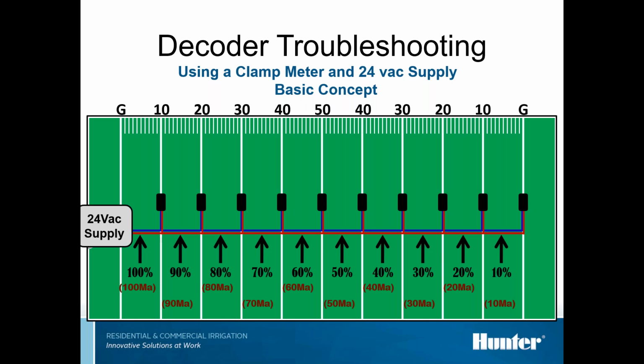And there's a representative of it, but they're using a 10 milliamp, which is perfectly fine too. You ought to be dropping every time you move your way down the line. Now, if you're doing the single decoder, it should just be 10, 10, 10, 10, 10. But if you're on the 2-wire path, it ought to be 100, 90, 80, 70, 60.